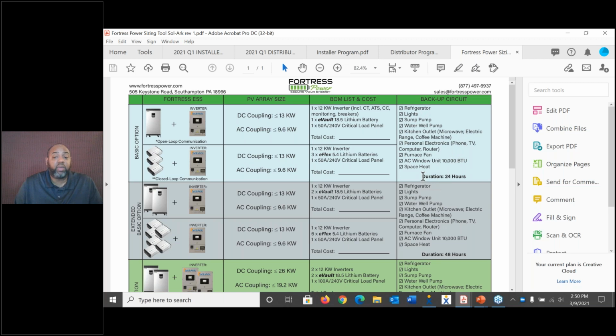If you look at the duration, it's 1 day. If you wanted to use an eFlex, going with that same mathematical principle, it would be 3 eFlex batteries to 1 solar inverter, and you could back up the same thing. This is going off that 2-hour design principle. So if you take this inverter, it produces 8 kW on the DC output side, which is basically 16 kilowatt hours of energy. So 5.4 times 3 pretty much matches you right up to that 16 kW. And notice this is 1-to-1 because this is 18.5 kilowatt hours of battery, using that same flow and flow management analogy.